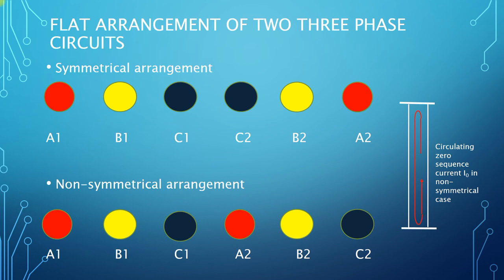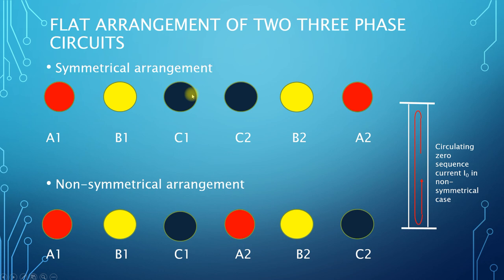If we had two three-phase circuits and we look up the standard textbooks, they will tell us that arranging the conductors A1, B1, C1 of circuit 1 and C2, B2, and A2 of circuit 2 will produce a symmetrical arrangement. With such a symmetrical arrangement, when we calculate the currents in circuit 1 and determine their sequence components, we will find that there is no apparent zero sequence current circulating around the two parallel three-phase circuits.